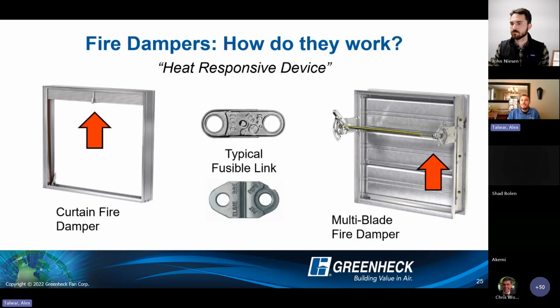So in terms of how they work, typically for a fire damper, we'll have a damper, either a curtain style damper like we see on the left there, or a multi-blade style fire damper that we see on the right there, held in the open position with some type of heat responsive device. Now, this is usually some type of fusible link that we see in the middle there. So that'll be hooked onto a couple of hooks on the curtain damper, holding that accordion-like blade stack in the open position. And then for the multi-blade, it's on a spring wound shaft. So once that link separates, that'll allow that spring to engage and the blades will slam shut on that multi-blade style product.